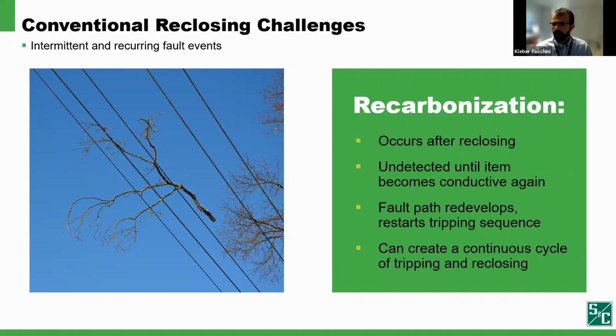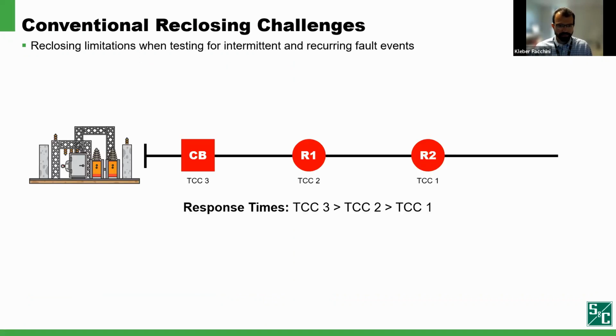Let me explain how it works. We'll run through an example here. I'm showing a typical feeder with two reclosers downstream of the substation circuit breaker. All of the devices here, for the sake of the example, are time current coordinated, meaning that the circuit breaker is set to a higher curve than the R1 recloser, and the R1 recloser is set to a higher curve than R2. This is configured in an attempt to only have the immediate upstream device of the fault trip. So let's see how it works.